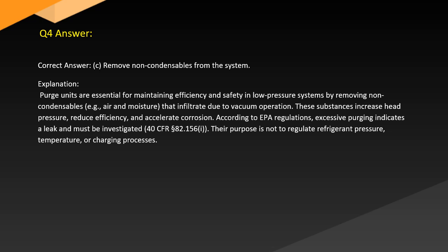Explanation. Purge units are essential for maintaining efficiency and safety in low-pressure systems by removing non-condensables, e.g. air and moisture, that infiltrate due to vacuum operation. These substances increase head pressure, reduce efficiency, and accelerate corrosion. According to EPA regulations, excessive purging indicates a leak and must be investigated. 40 CFR 82.156. Their purpose is not to regulate refrigerant pressure, temperature, or charging processes.